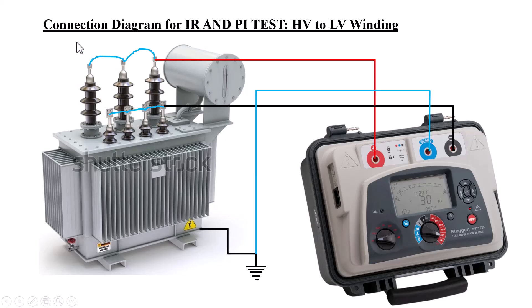In the figure, we have the megger instrument — it is a 15 kV insulation resistance tester, the MIT 1525. This is not compulsory; it may be 10 kV or 5 kV depending on the test set. Some test sets have a range of 10 kV. We need to perform the test at 5 kV, and you can see the selection knob. The current selection is 15 kV, but this test set is just for visualization purposes to give you an idea of how it looks.